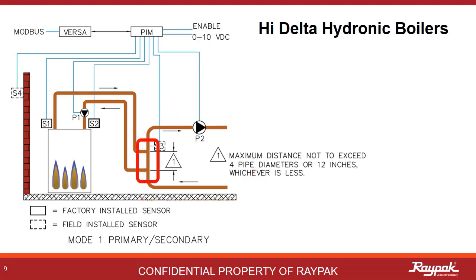The place where the two loops overlap is called the decoupler. The decoupler is the magic of a primary-secondary system. When built properly, this will allow the bigger system pump to run when the boiler is not running without forcing water through the boiler.